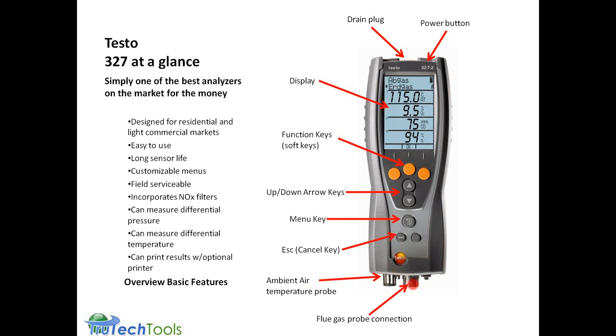The flue gas probe connection is this metal ferrule on the bottom. You can see kind of the locking ridge that's inside there. So when you place your hose connection up over it and you give it a twist to the right, it will lock it in place. Very secure connection with a lot of good strain relief on it. So there's no danger or worry of loosening the connections or losing contact when you're in the middle of making a measurement.